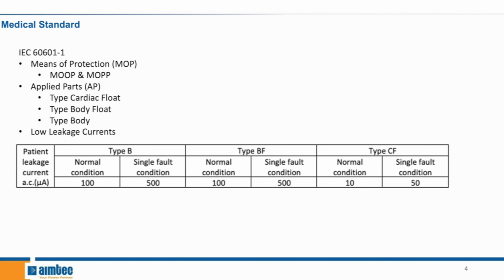As patients may not be able to react to electrical shocks, stricter protection requirements are applied for means of patient protection. Means of protection can be achieved by creepage, clearance, and protective earth connections, also known as your ground. Based on the working voltage of the medical equipment and devices, different distances of creepage, clearance, or tests are defined. For certain medical devices, 2 times MOPP or 2 times MOOP may be required.